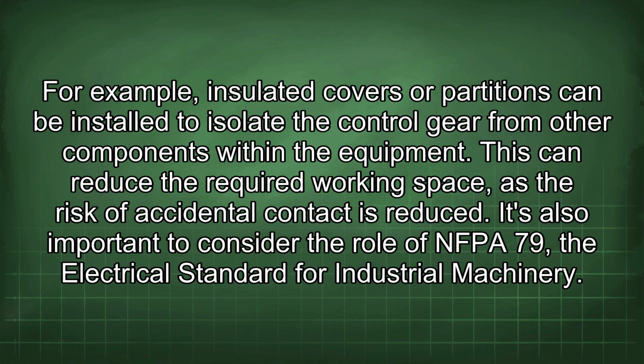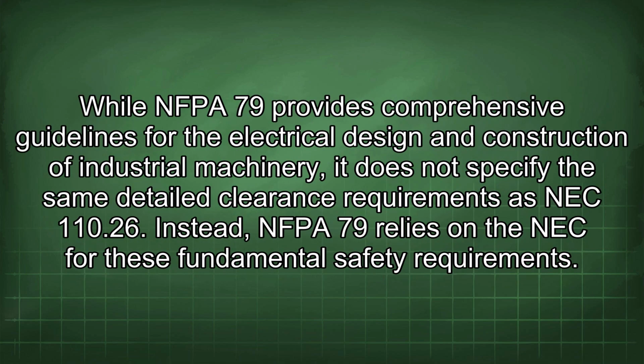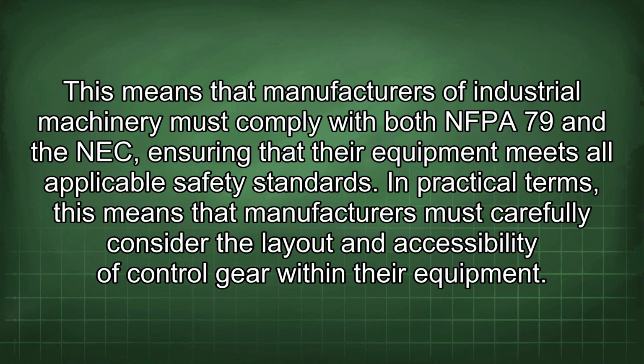It's also important to consider the role of NFPA 79, the electrical standard for industrial machinery. While NFPA 79 provides comprehensive guidelines for the electrical design and construction of industrial machinery, it does not specify the same detailed clearance requirements as NEC 110.26. Instead, NFPA 79 relies on the NEC for these fundamental safety requirements. This means that manufacturers of industrial machinery must comply with both NFPA 79 and the NEC, ensuring that their equipment meets all applicable safety standards.